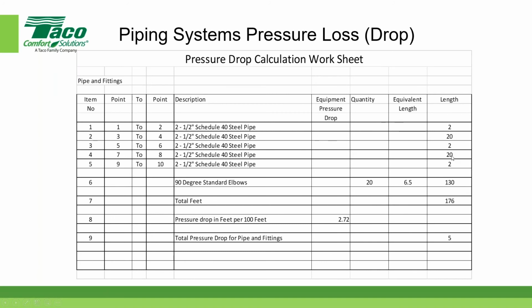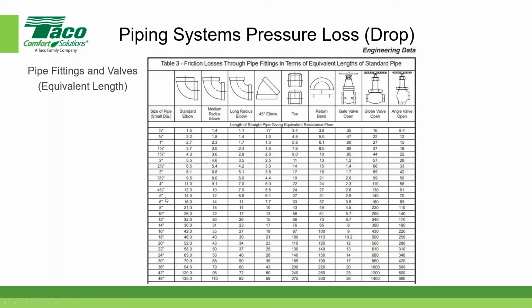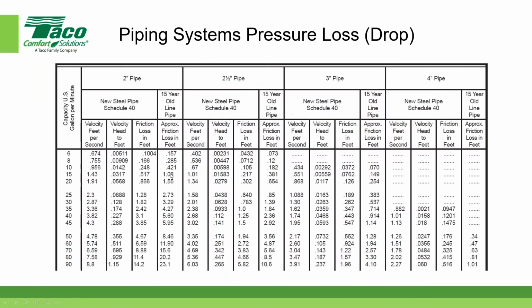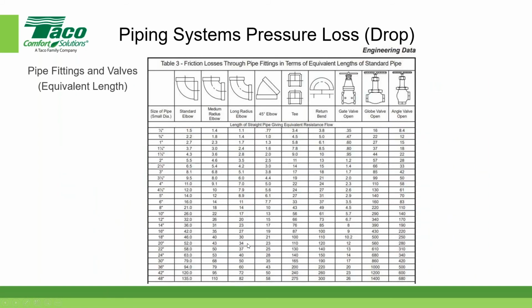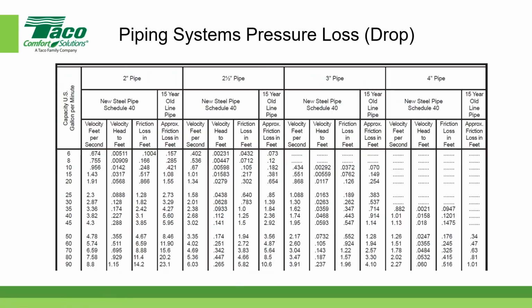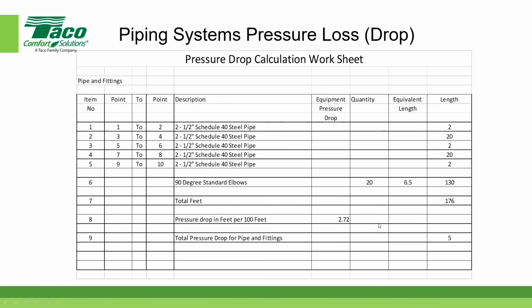So if I just do my arithmetic out, 20 plus 20 is 40, 42, 44, 46, and 130 is 176. That's the total length of pipe and equivalent length of fittings that's in my system. And the pressure drop in feet per 100 feet is 2.72. Again, going to my table for 2.5 inch, I went the wrong way. Yes, here it is. For 2.5 inch pipe running at roughly 60 gallons per minute, it's 2.72. So that's how I came up with that pressure drop of 2.72 feet.